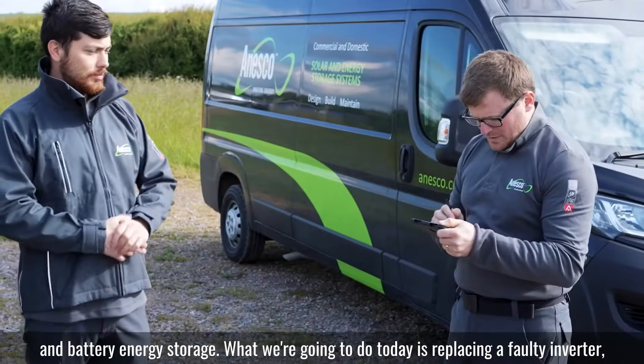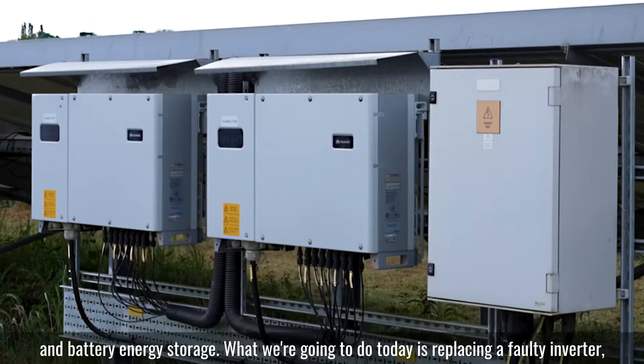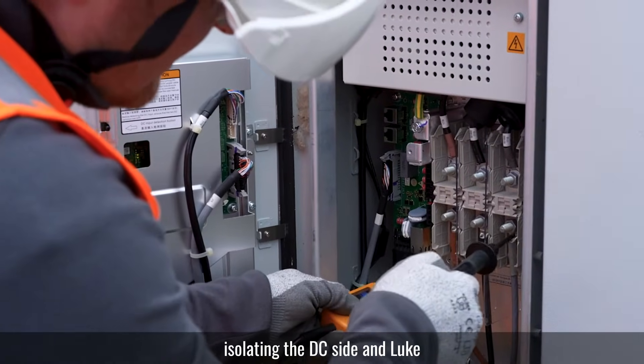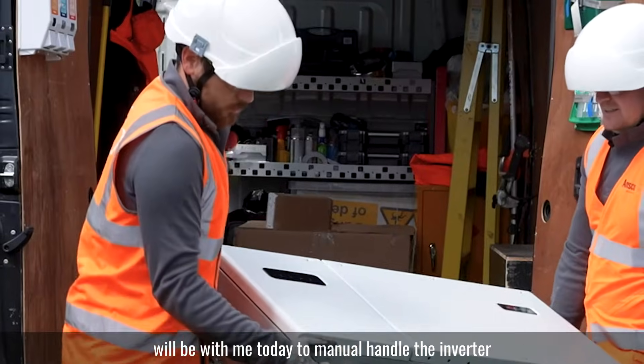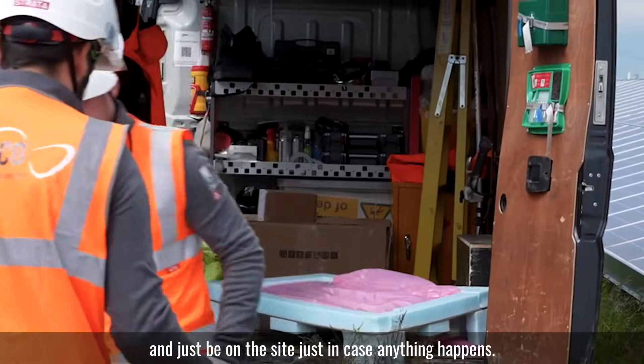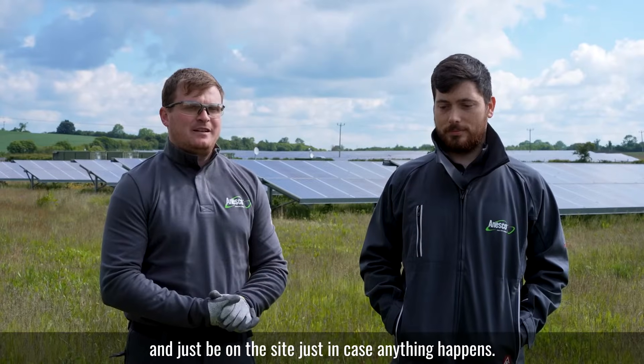What we're going to do today is replacing a faulty inverter, which involves isolating the AC circuit, isolating the DC side. Luke will be here with me today to manual handle the inverter and just be on the site just in case anything happens.